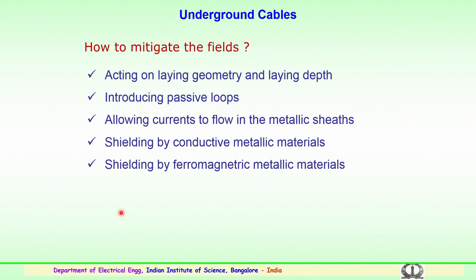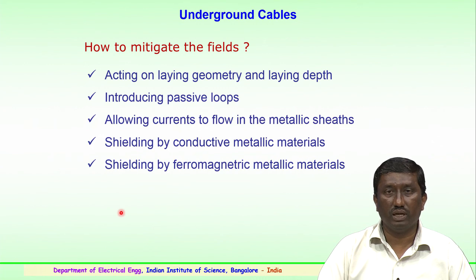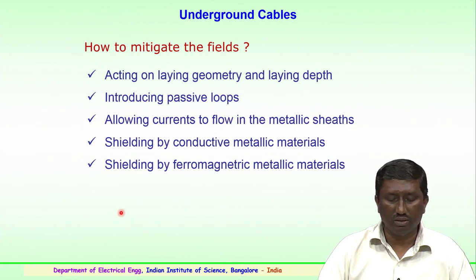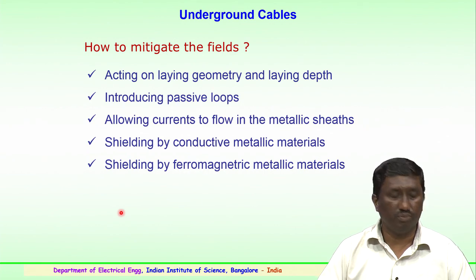How to mitigate the fields, particularly for the underground cables? For the overhead conductors, we have seen. For underground cabling, again it depends on the laying geometry, how the cable is laid, and what depth of cable trench is adopted for the voltage and the dimension of the cable. So, here also introducing passive loops could help in reducing the magnetic fields, also allowing currents to flow in the metallic sheath of the cables. Then shielding by conductive metallic materials will further help in reducing the magnetic fields of the underground cables, and shielding by ferromagnetic metallic materials will also help to reduce the fields.